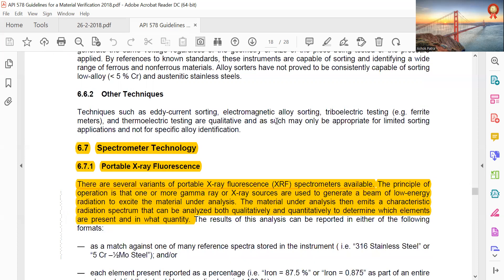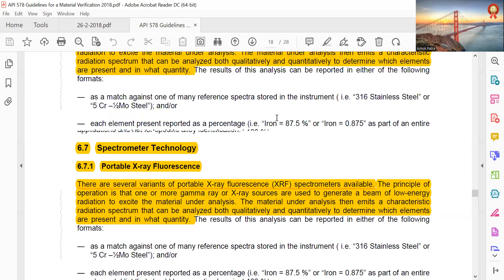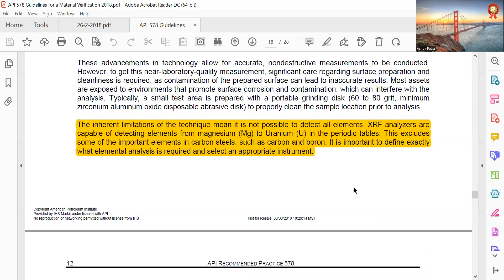Portable X-ray Fluorescence, XRF: there are several types of portable XRF spectrometers available. The principle of operation is that one or more gamma ray or X-ray sources generate a beam of low energy radiation to excite the material under analysis. The material then emits a characteristic radiation spectrum that can be analyzed both qualitatively and quantitatively to determine which elements are present and in what quantity. The inherent limitation of this technique is that it cannot detect all elements — XRF analyzers can detect elements from magnesium to uranium, but exclude some important elements in carbon steel such as carbon and boron. It is important to define exactly what elemental analysis is required and select an appropriate instrument.